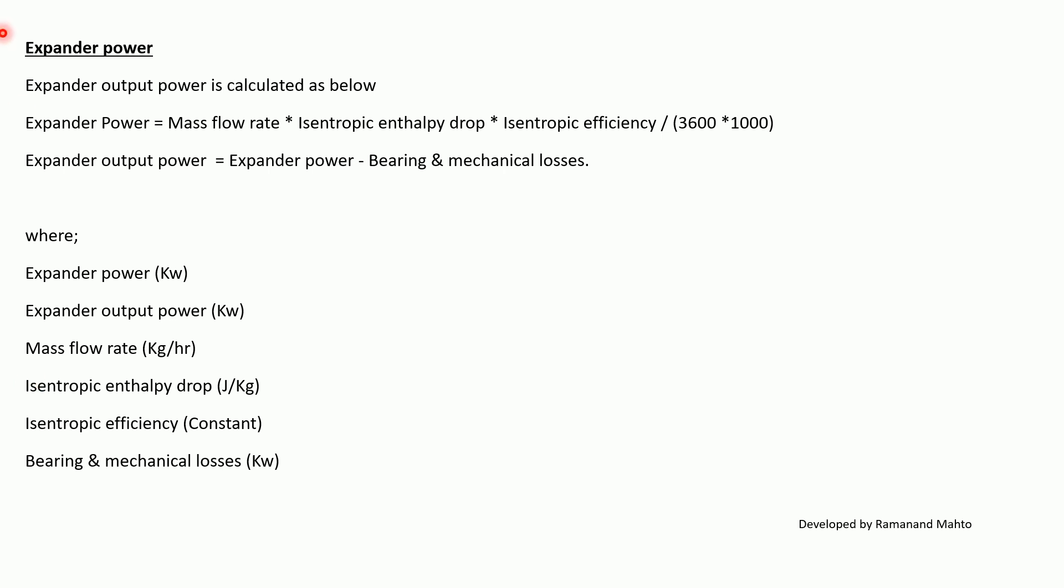Now expander power: expander output power is calculated as below. Expander power is equal to mass flow rate times isentropic enthalpy drop times isentropic efficiency upon 3600 times 1000. Expander output power is equal to expander power minus bearing and mechanical losses.